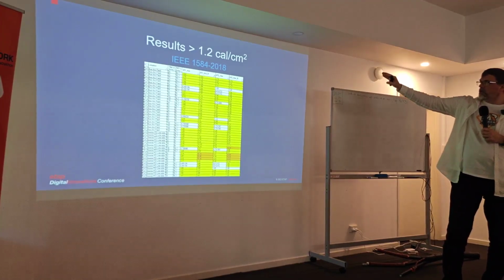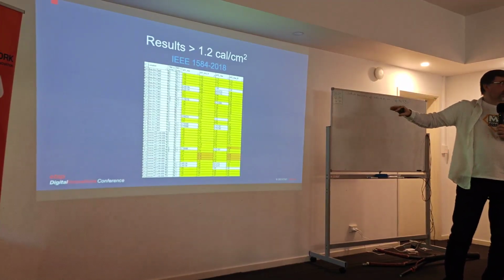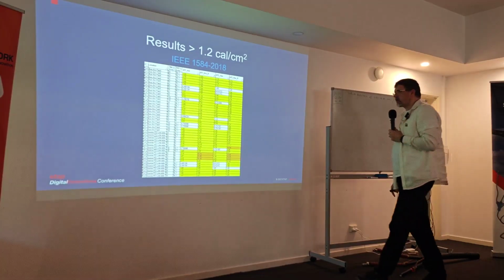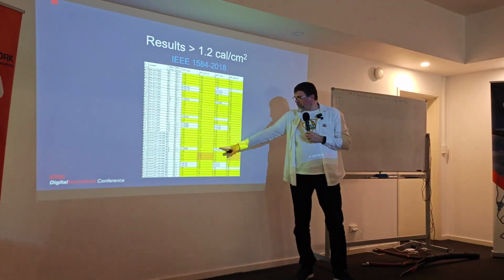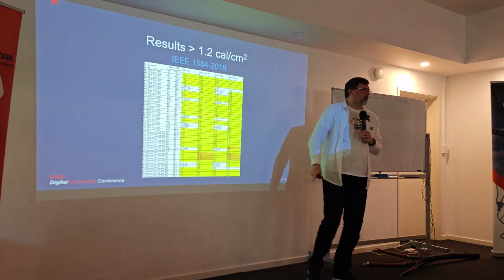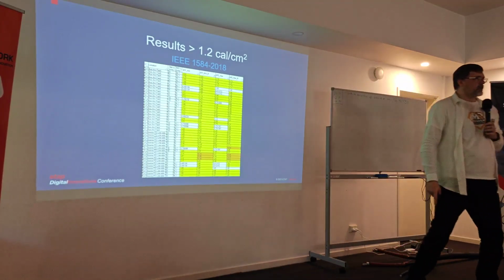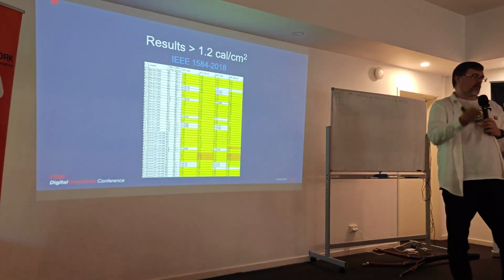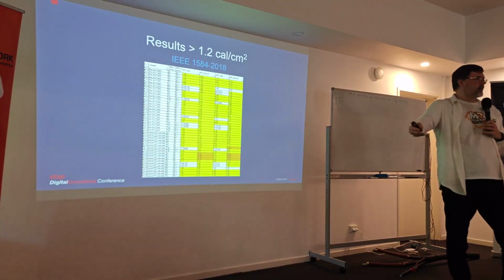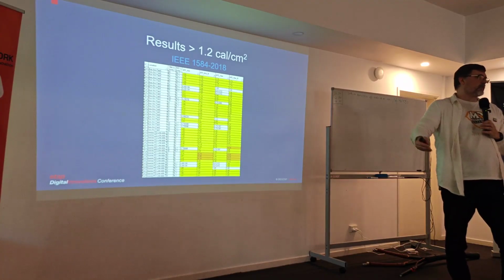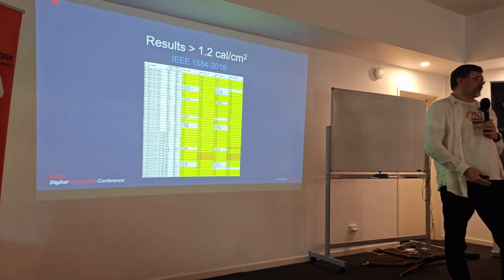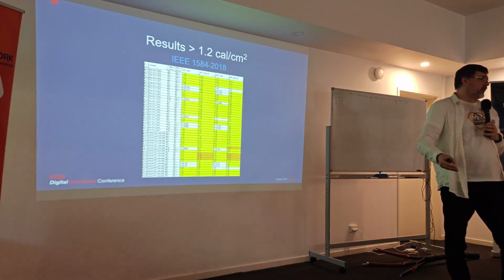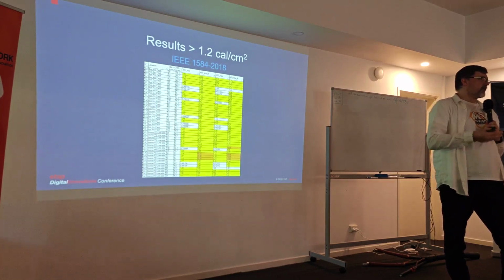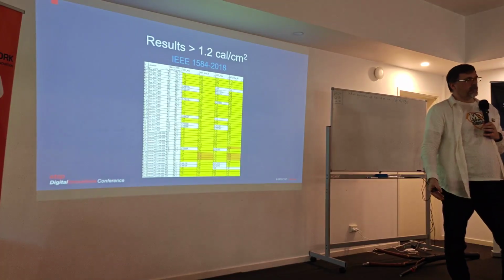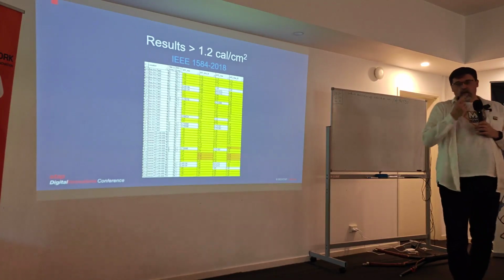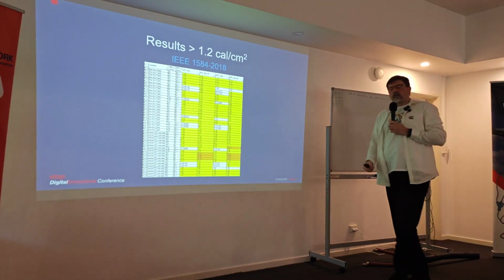So you have multiple scenarios, then you can start to see the worst case. And the thing is that you can see that there is a drop from 3 to 1.2. When we do a recommendation for the setting, sometimes you also increase the energy. We try to just keep it in the same PPE category area. Because if you have a 2.5 and you can make it better from protection and make it 6, it's not good from safety, but overall you have the same PPE on yourself. So it's an acceptable solution, let's say.